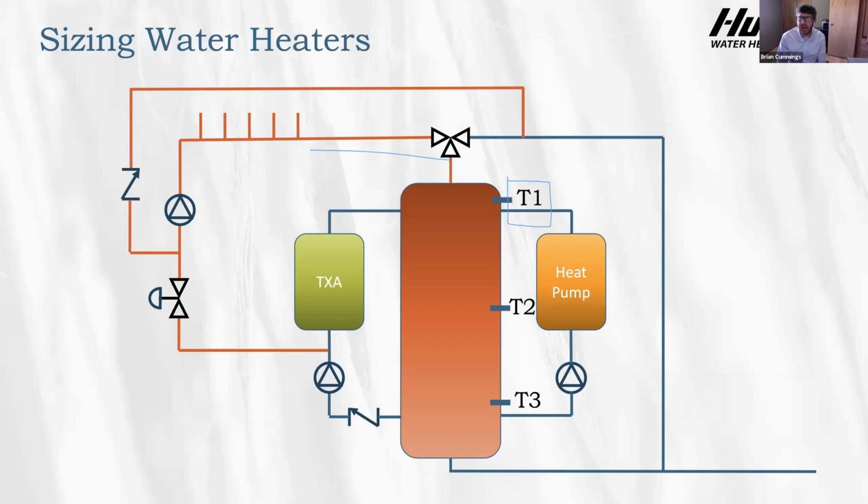Now, the other reason that we don't do that with hot water is because there's somewhat intermittent loads. You're not always running your hot water heater or your heat pump or anything like that. And again, for building chiller loops, they want to make sure the temperatures are very tightly controlled. So are there mixed systems out there? Yeah, there are. There are people that mix these and try to utilize them. And if you have cold air use for it, yeah, you could do it, but let me put it another way, it's controlling the output temperature of the water, not the output temperature of the air. And because of our control method there, we can't guarantee you're going to have the right temperature air or, we'll say, water glycol mixture coming out of the unit so that it will work with the rest of the building. So yeah, that's a very good question.